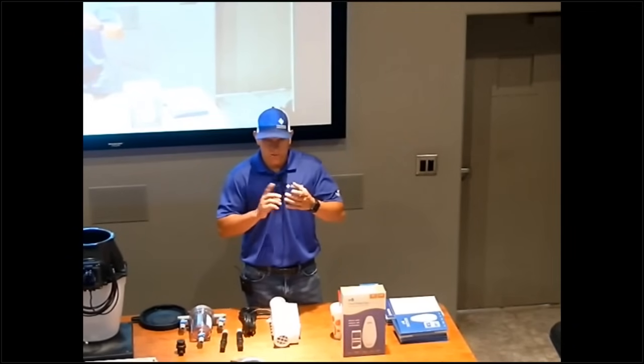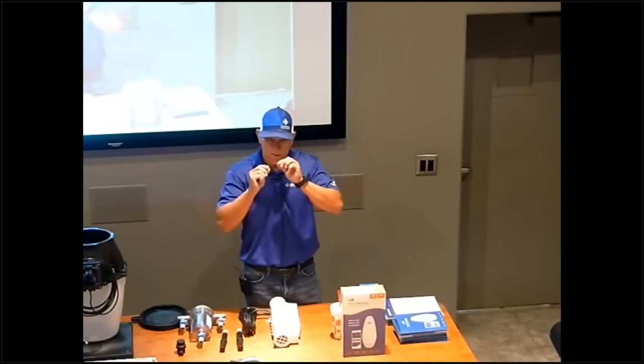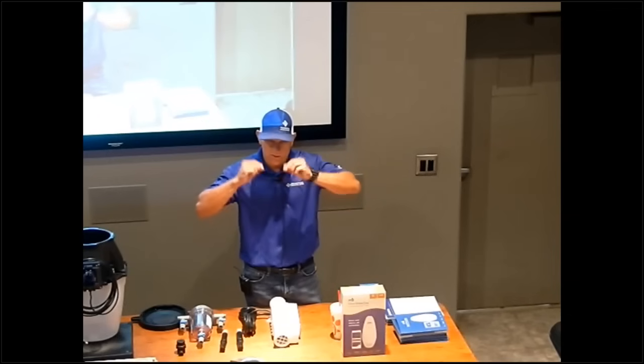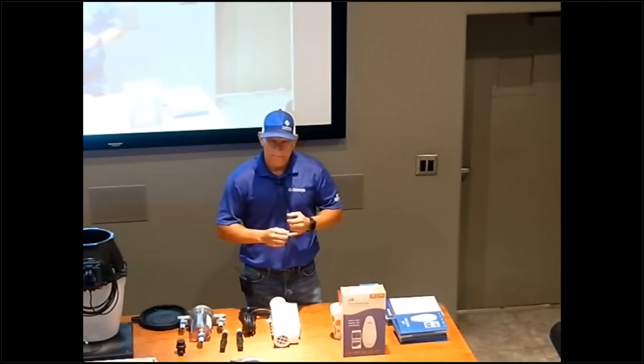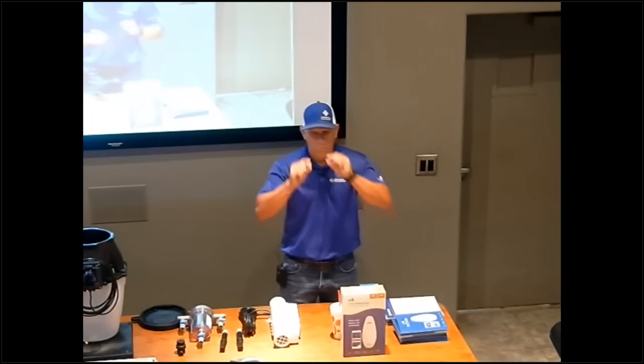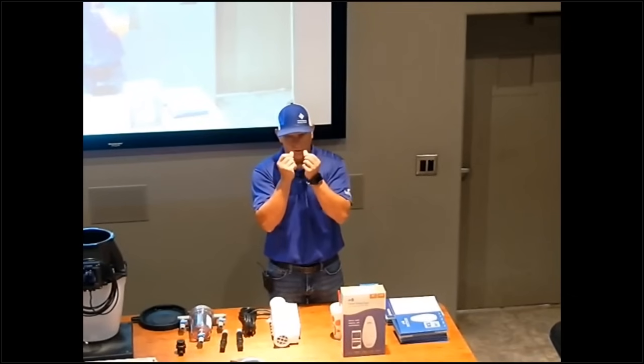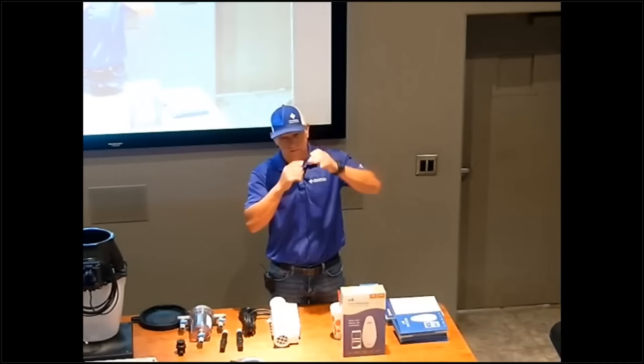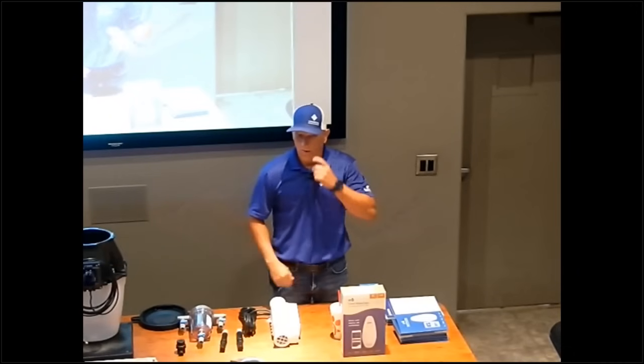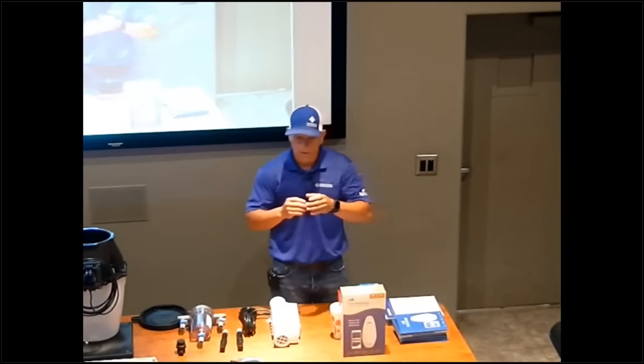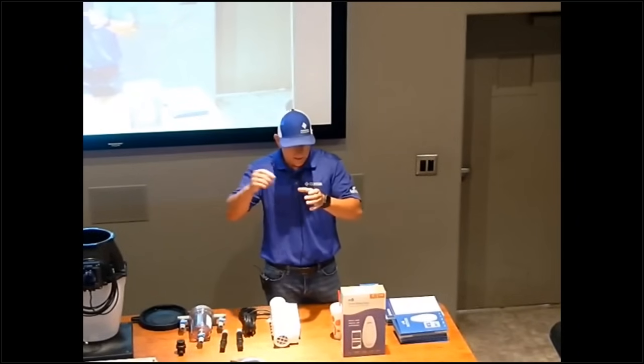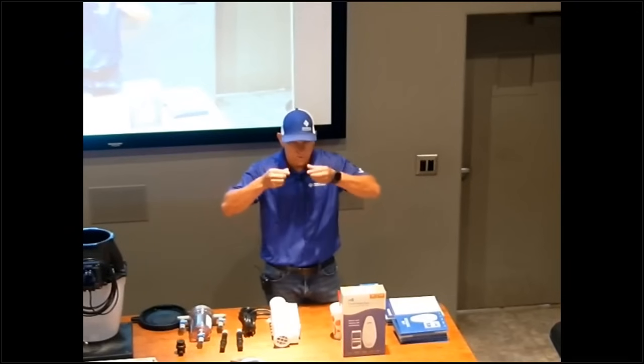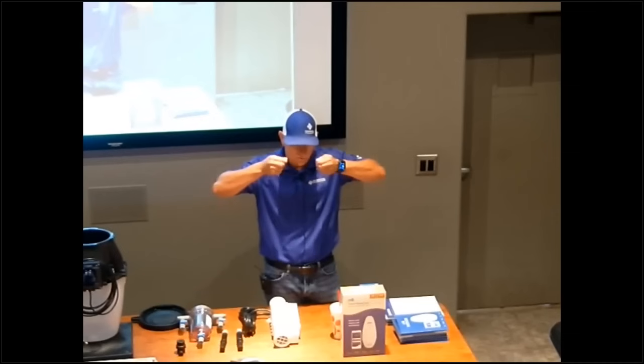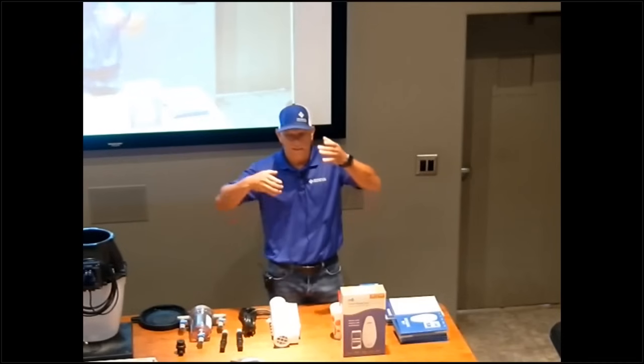Anytime you take the union off, there's an O-ring. I recommend just popping the O-ring out, wiping it dry, and flipping it over. It has to have an O-ring on both the top and bottom - it's there, it would leak like a sieve without it, it would pour water out without them. They're just black and blend in pretty well. You should be able to feel it in the seam, because without that O-ring it would stream water out of the top and bottom for sure. So just check that. Make sure when you unthread it, get the cell out, pop the O-ring out, wipe it dry, and flip it - rotate it - so it's nice and clean, then get it back in there.